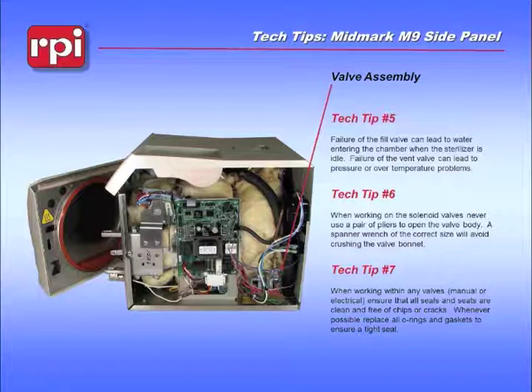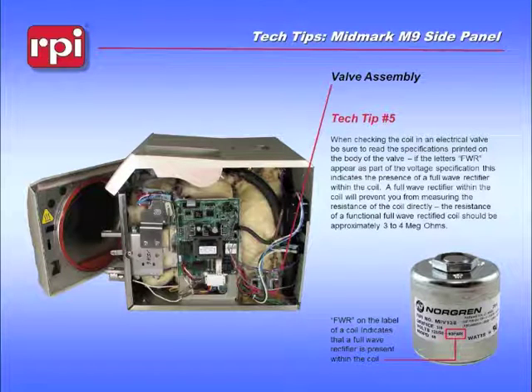You want to make sure if you do go into these valves that everything is clean, that the sealing surfaces are clean and undamaged, and in particular you want to take a look at the sealing surface within this brass block to make sure that it doesn't have any chips in it, or the sealing surface within the top of the bonnet on the vent valve to make sure that it is solid, doesn't have any gunk built up on it, or chips, to ensure a tight seal. Okay, moving to the actual valves.